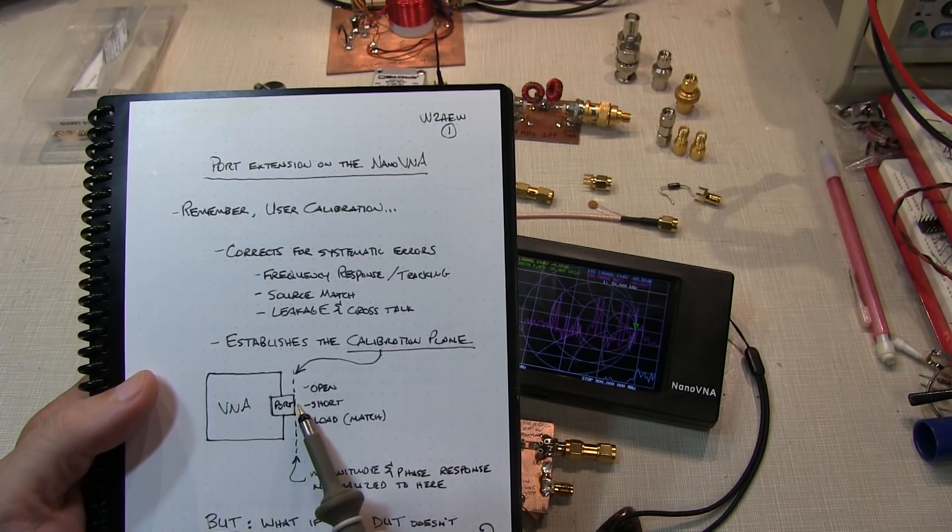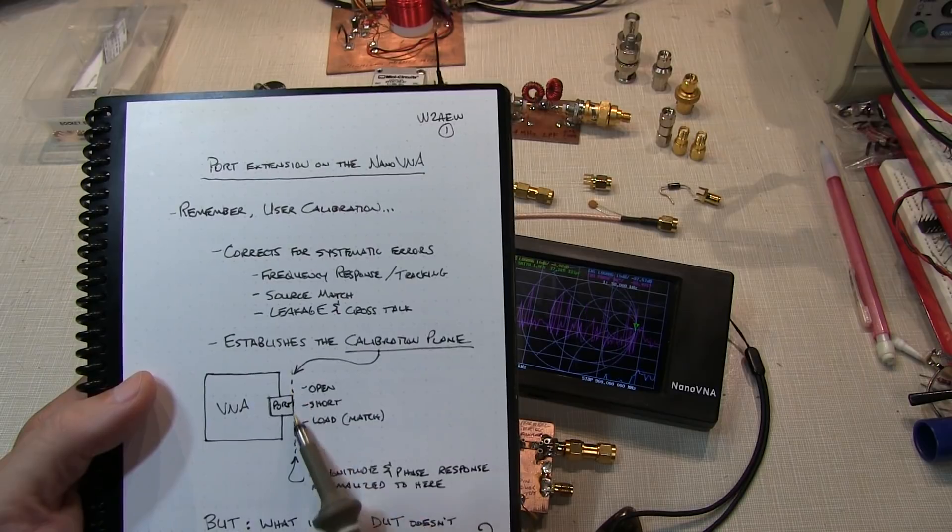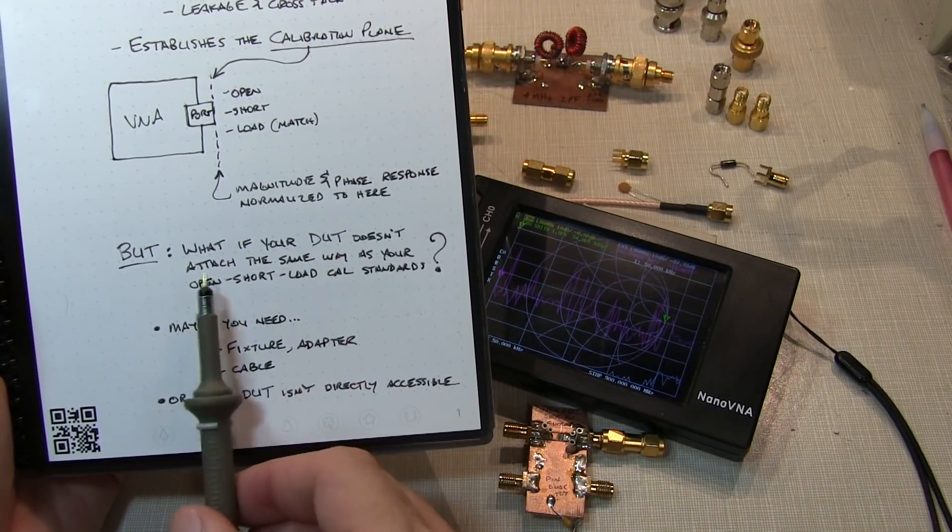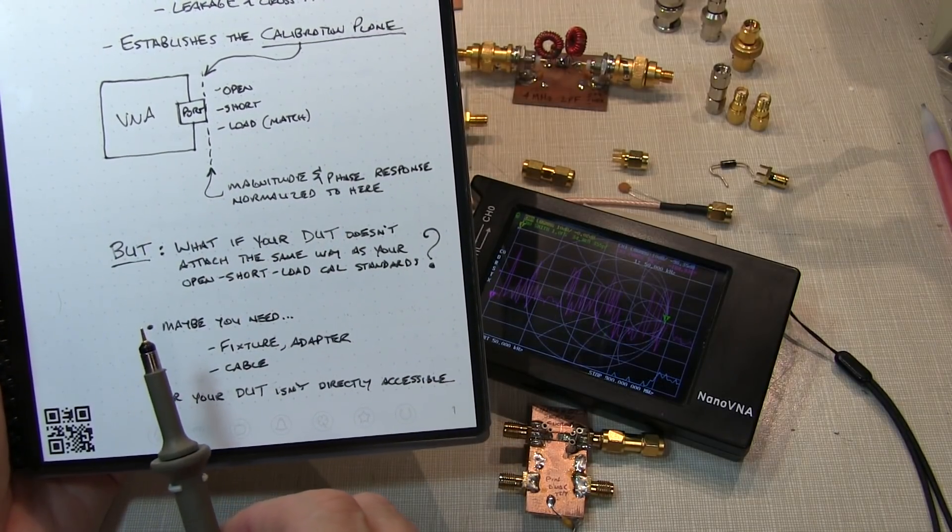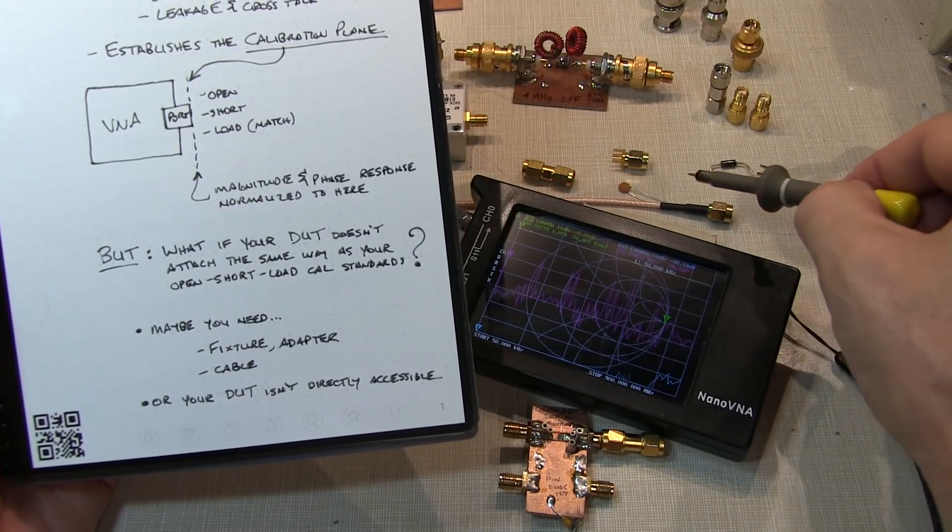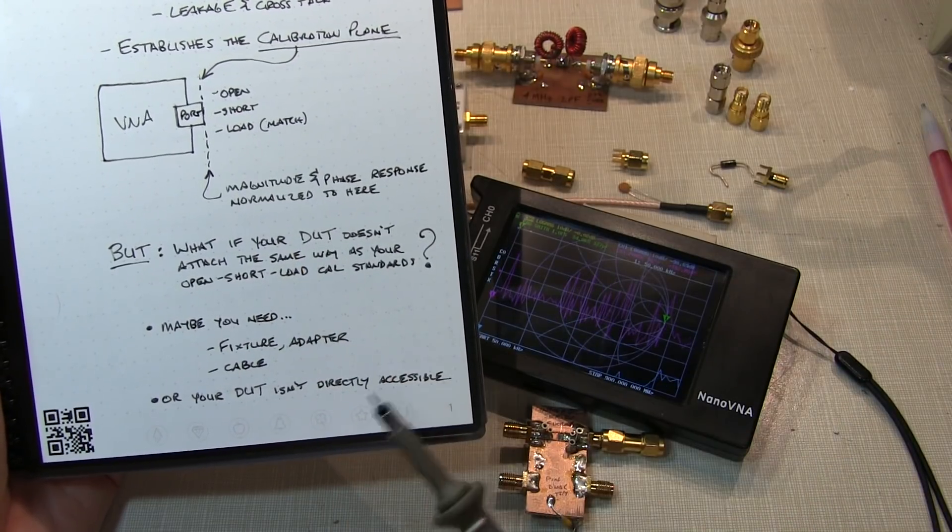But what if the device you're testing doesn't attach the same way as your open, short, and load standards that you use for calibration? Maybe you need some kind of a fixture, or maybe an RF adapter, or even a short length of cable to connect your device under test to the VNA.